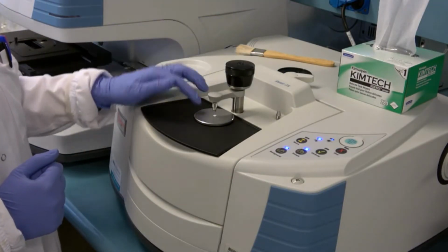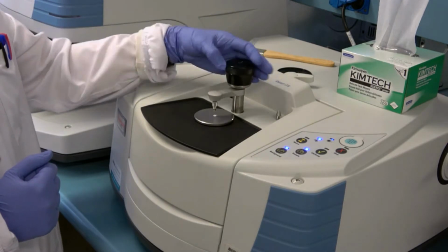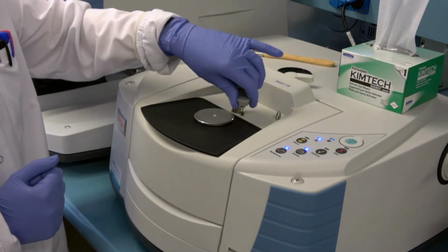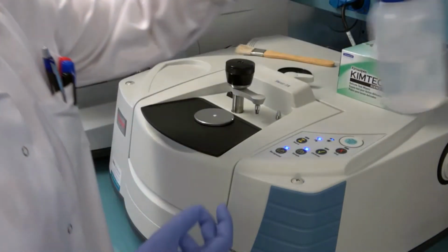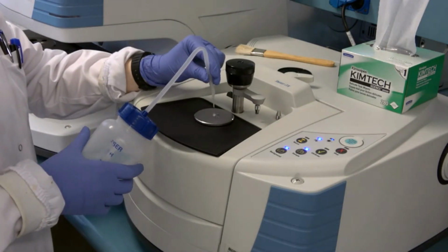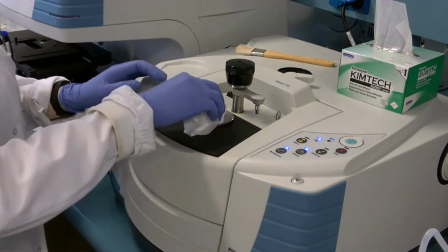After analysis, the instrument must be cleaned. The pressure pin is removed off and the arm moved to the side. First, the sample must be removed. This is done with either a tissue or a brush.